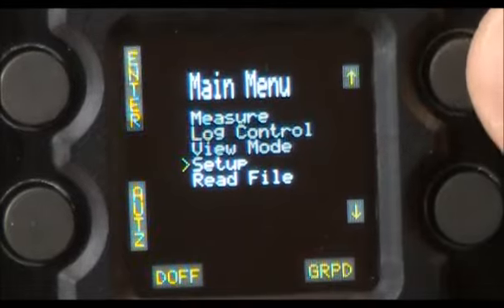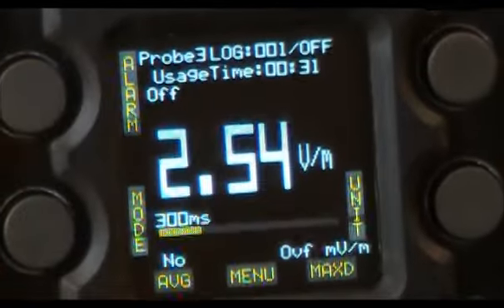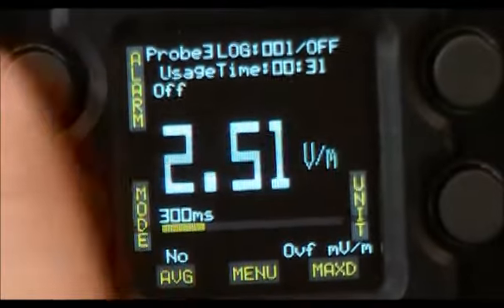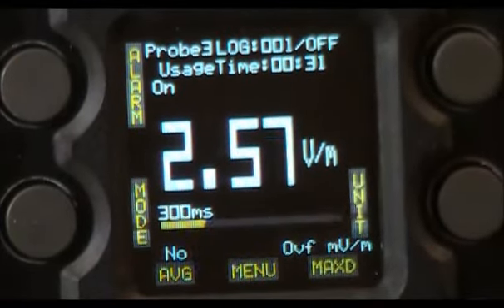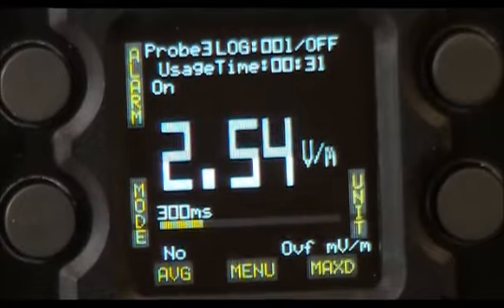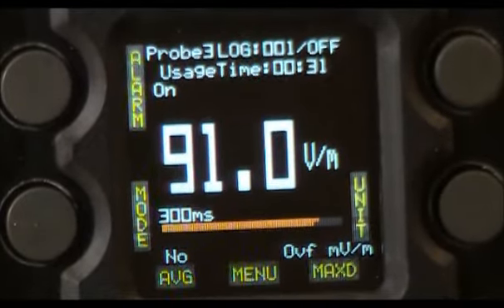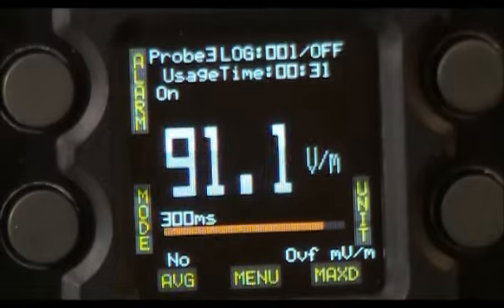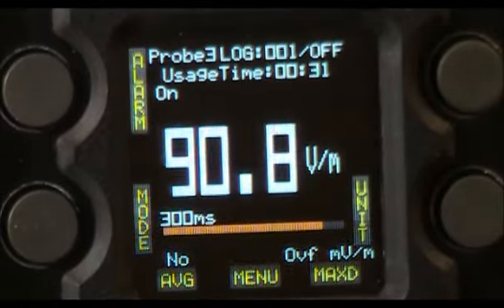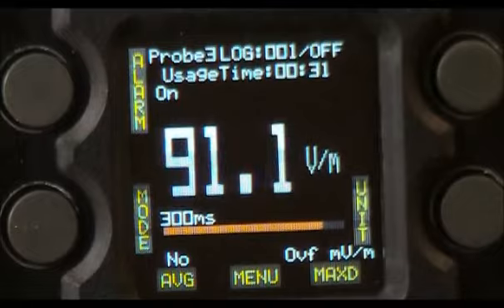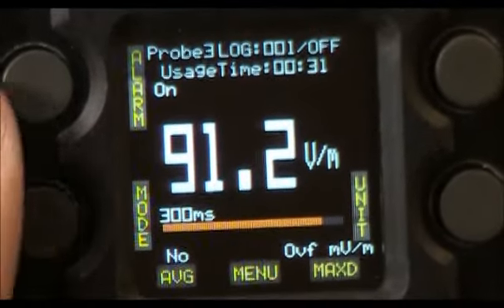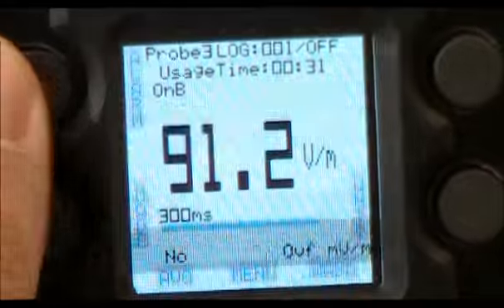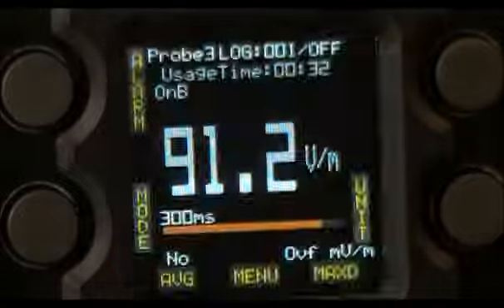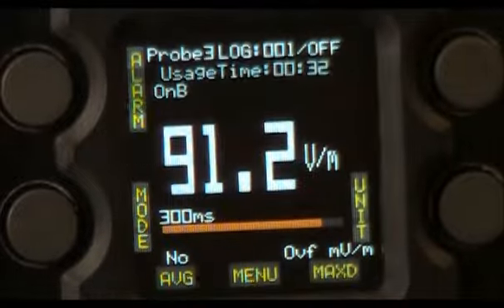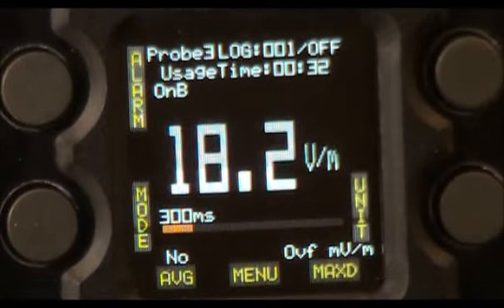Push menu back. Now you go to measure, enter. Now you're on the main screen, and now turn on alarm. Now alarm is on. So if I now change the field, so field will be higher than that, you get indication. Field is about 90 volts per meter and you preset alarm to 50, so you get indication. If you choose second mode, you will also get sound and blinking screen indicating that you exceed the field. If your field gets down, alarm will stop.